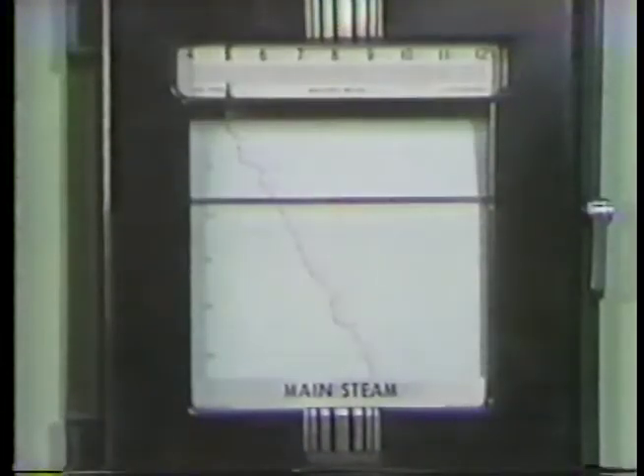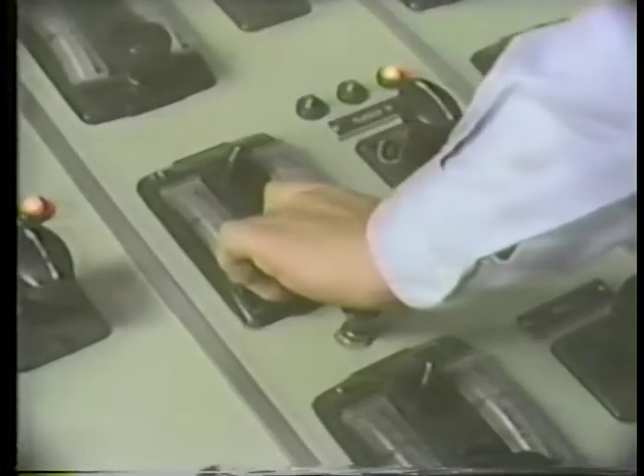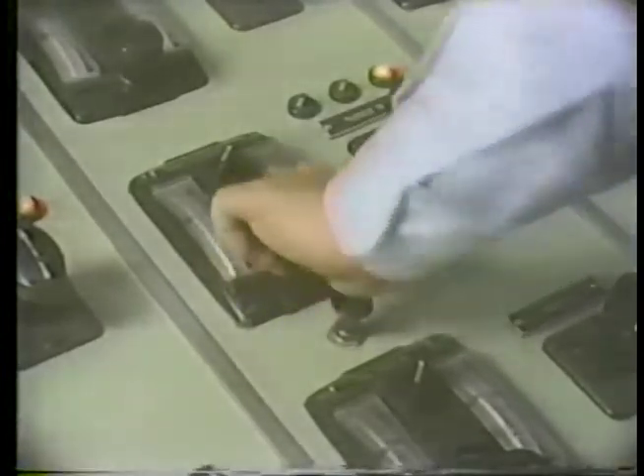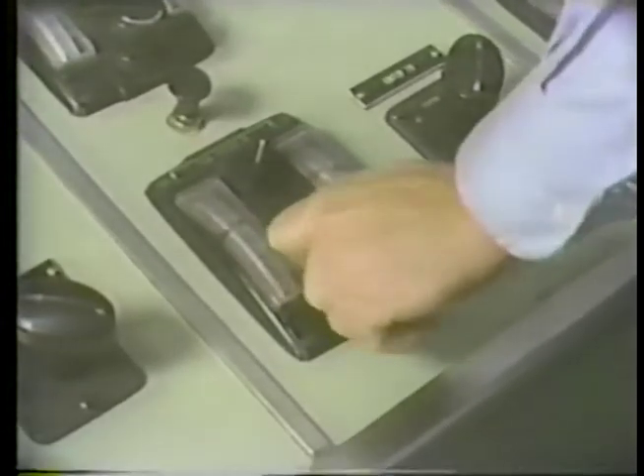The first step in shutting down the boiler is to reduce the firing rate according to proper procedures. Reducing the firing rate affects the temperature and pressure on the boiler. As with startup, temperature and pressure must be reduced gradually to protect the boiler. This is known as ramping down, and in this plant, the operators reduce the firing rate no faster than 150 degrees Fahrenheit per hour. Check your procedures for rate acceptable for your boilers. As load decreases, the operator begins to reduce the fuel flow to the burners. This is done by taking pulverizers offline one at a time.